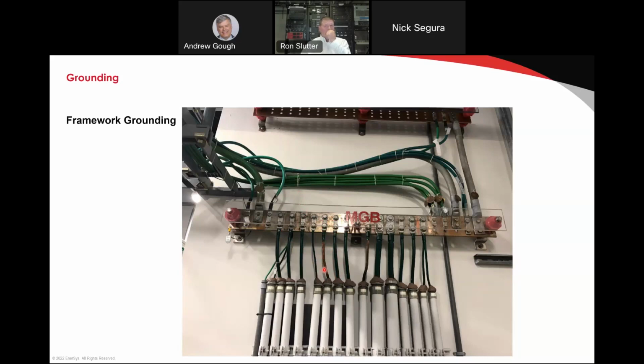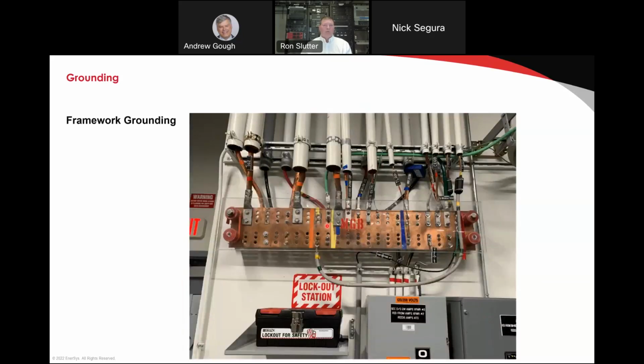So the installation practices that you have for your grounding are extremely important. If you don't capture this when all of the grounding is installed and you get a lightning strike near your building, you're going to suffer extensive damage. And you're going to say, I've got all of these ground conductors installed. Why is it not working? It's not working because of the chokes that are in your existing system. I see this everywhere. Just to give you a few examples.